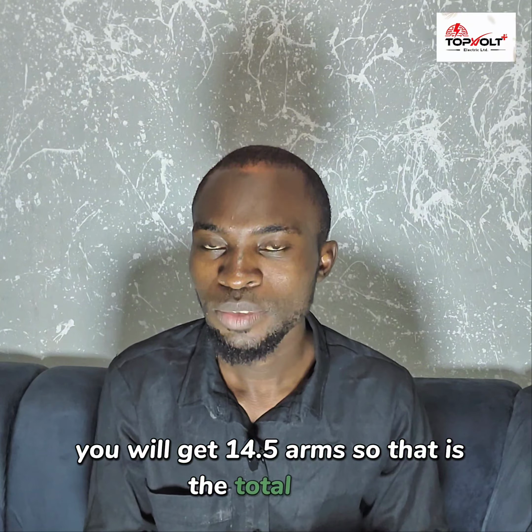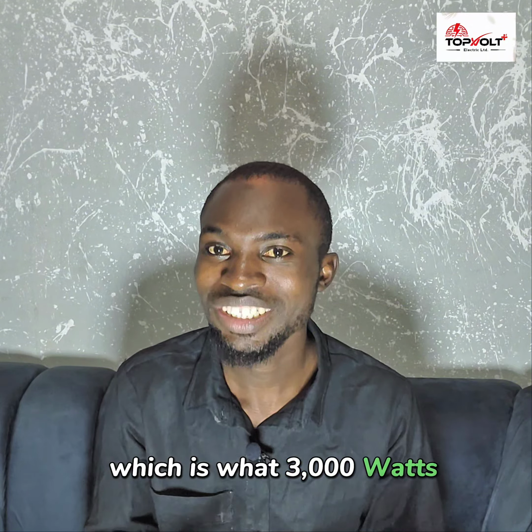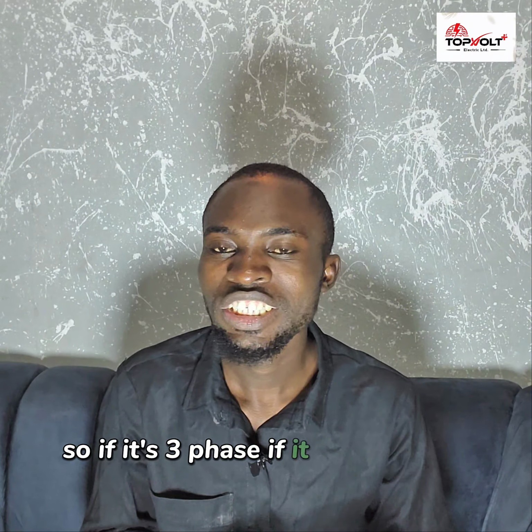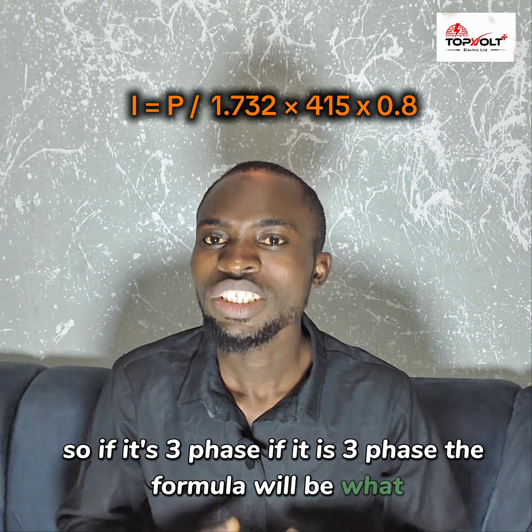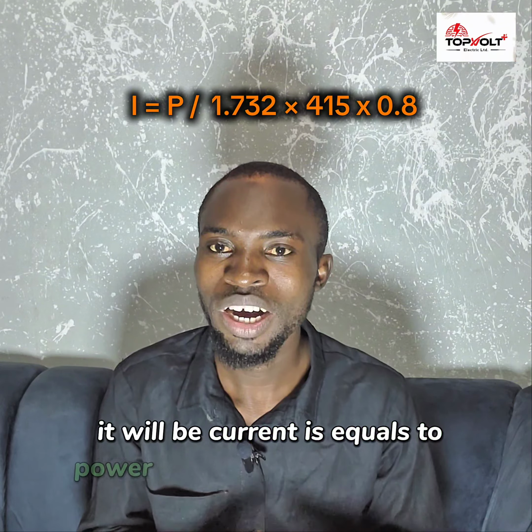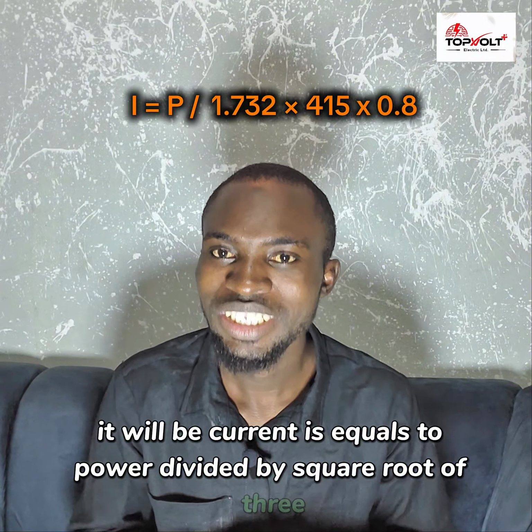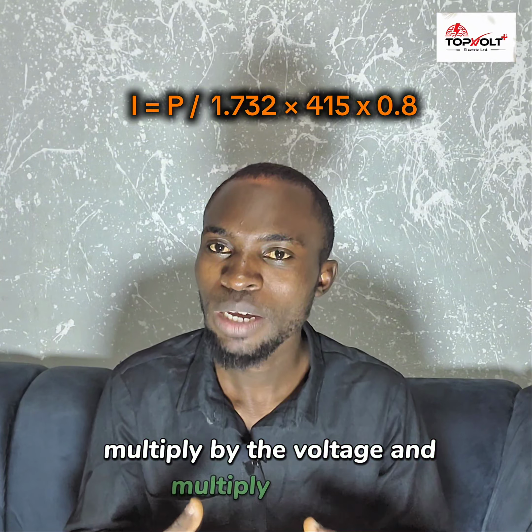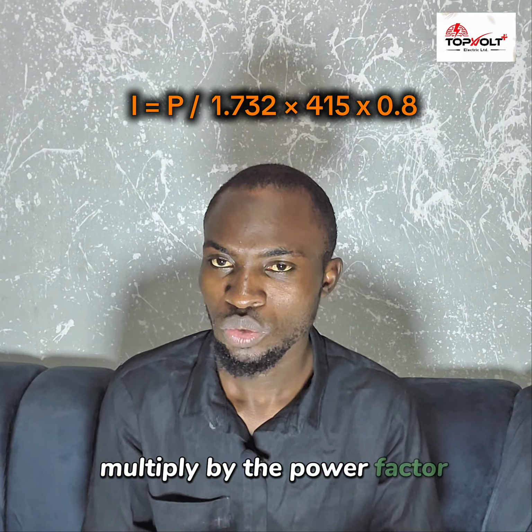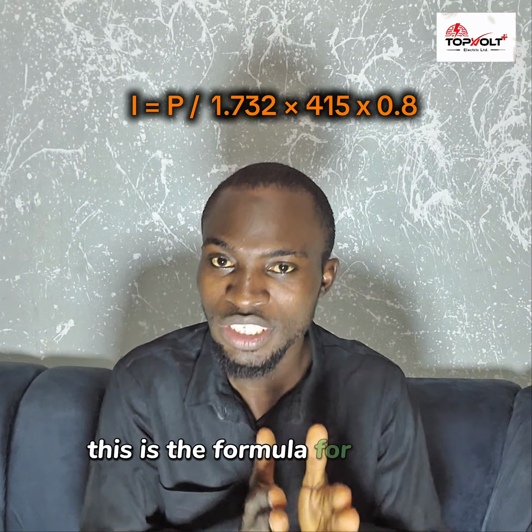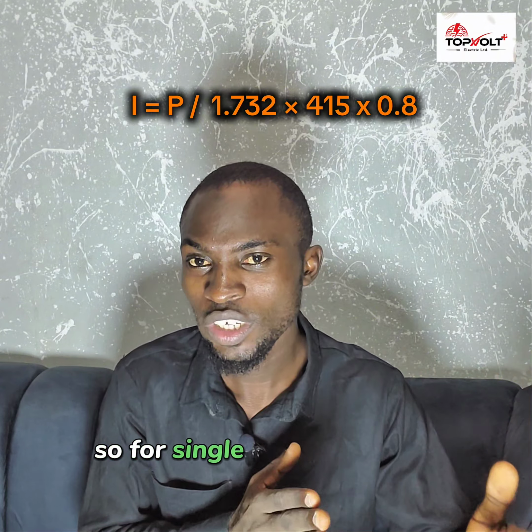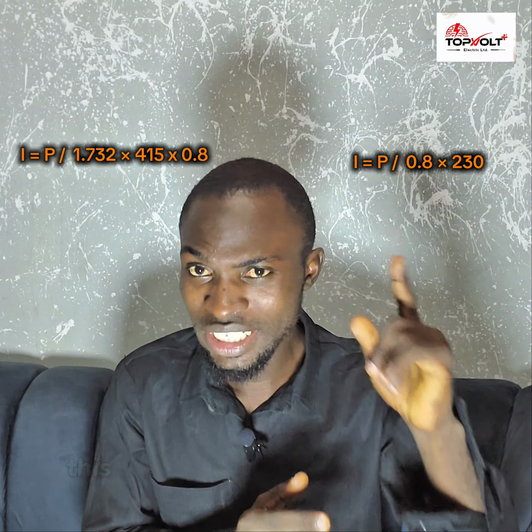That is the total amps that you need for your power, which is 3000 watts. So if it's 3-phase, the formula will be what? The current is equal to power divided by square root of 3 multiplied by the voltage and multiplied by the power factor. This is the formula for 3-phase. So for single phase, this is the formula. But for 3-phase, this is the formula.